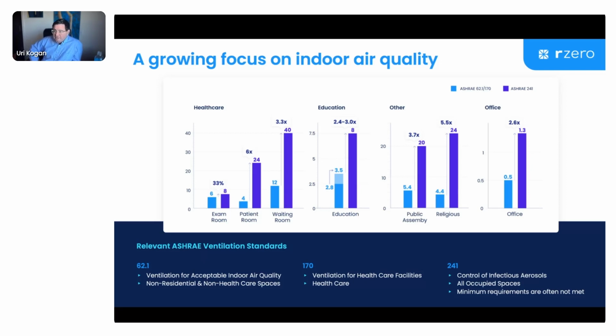LEED also added a recommendation to use MERV 13 filters. If you've moved from lower quality to higher quality filters in your building, you already know there's an energy penalty to pay for that. Not only are the filters themselves more expensive, but the cost of running your HVAC and pushing air through those filters is generally a bit higher too.